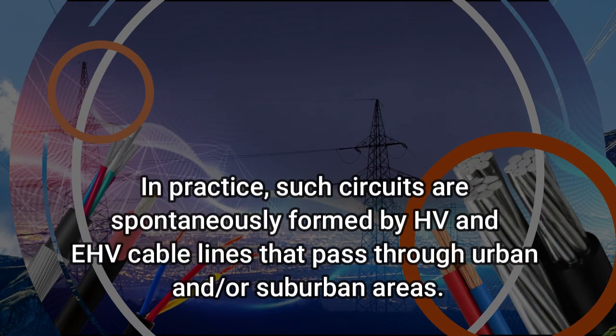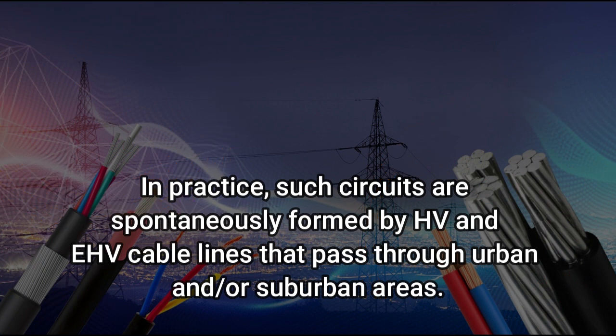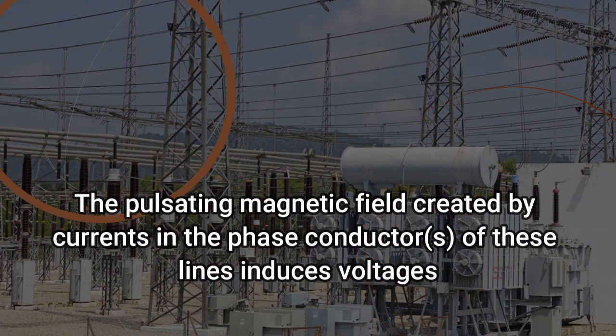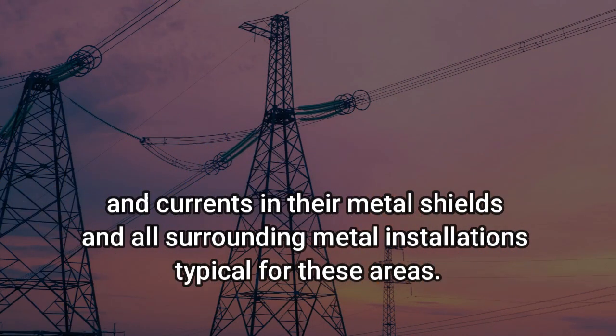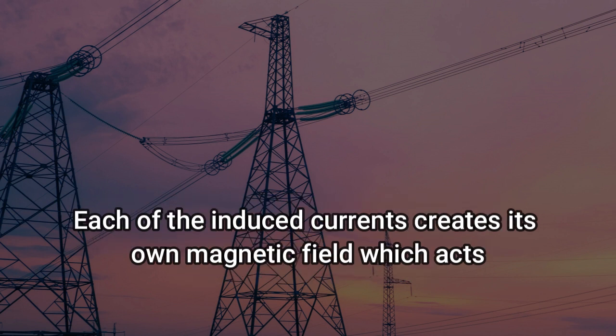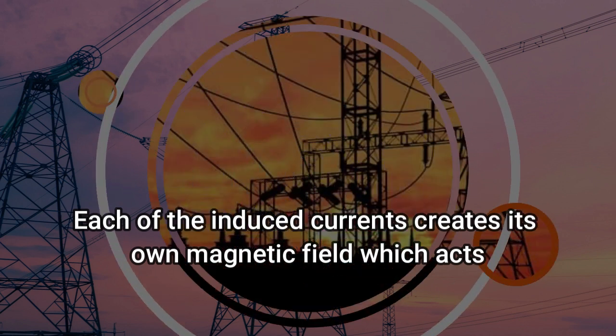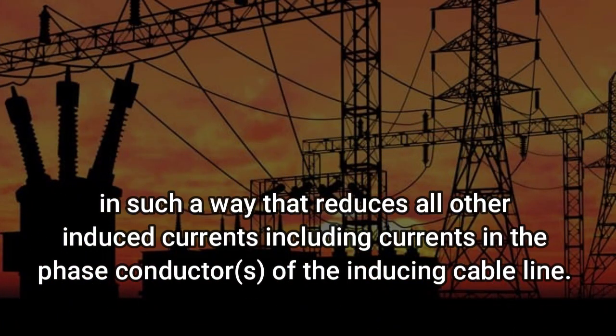In practice, such circuits are spontaneously formed by HV and EHV cable lines that pass through urban and/or suburban areas. The pulsating magnetic field created by currents in the phase conductors of these lines induces voltages and currents in their metal shields and all surrounding metal installations typical for these areas. Each of the induced currents creates its own magnetic field, which acts in such a way that it reduces all other induced currents, including currents in the phase conductors of the inducing cable line.